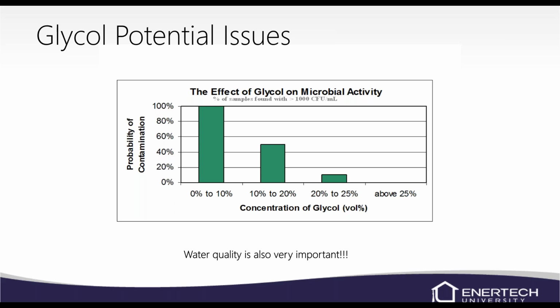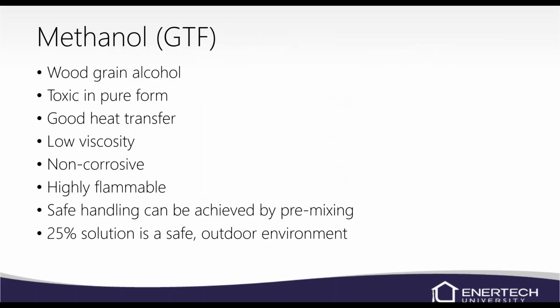To be honest with you, any antifreeze does, because here we've got methanol or GTF. It's alcohol-based, a wood grain alcohol. It's toxic in its pure form. It does have good heat transfer because it's real light, low viscosity. It's non-corrosive, but it can be highly flammable. So anything above 25% could be flammable. Anything 25% and less, and then you're safe.